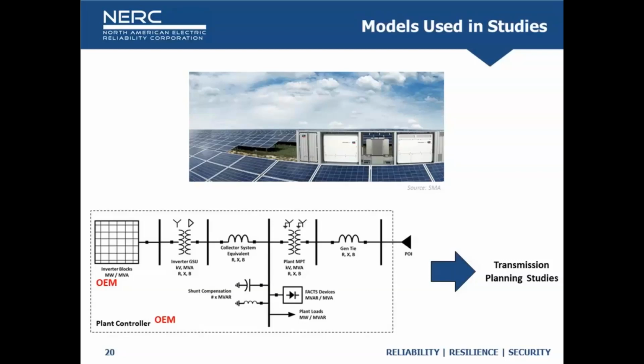Now someone has to compile that all into an aggregate model, where an inverter may need to represent 1,000 inverters or 100 inverters, and a plant-level controller needs to represent how this all works together. Then you have to add in all those other components, like the collector aggregate and the main power transformer. Typically that's a consultant or somebody executing that for the developer or the generator owner.